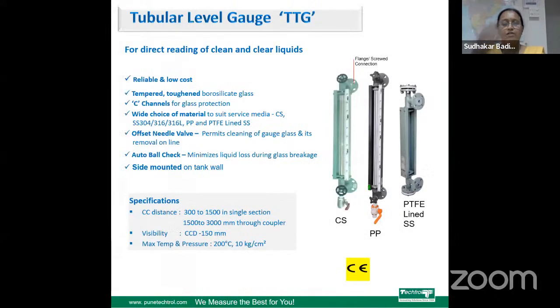So the first one is tubular level gauge. This is used for direct indication of liquid level in the tank, and that liquid should be clean and clear. This is a reliable and low cost instrument. It uses tempered toughened borosilicate glass, and this borosilicate glass is protected with C channels. Wide choice of material is available in stainless steel, then PP and PTFE lined SS.